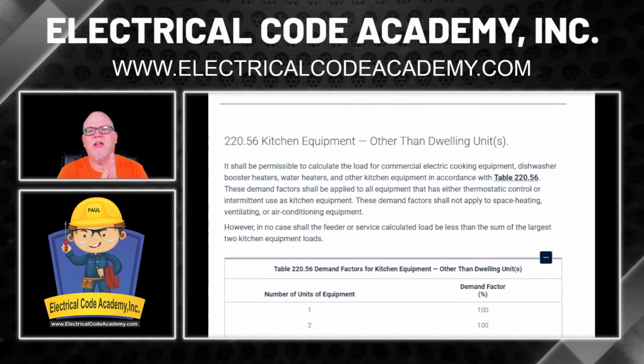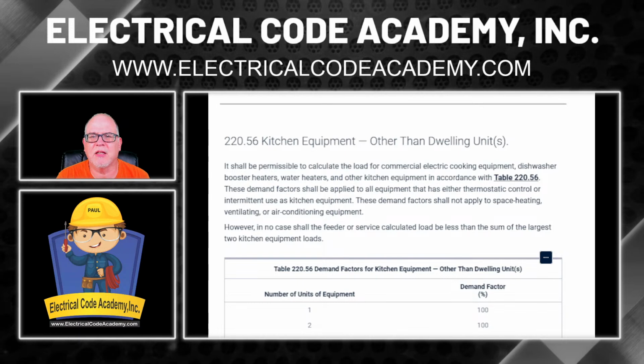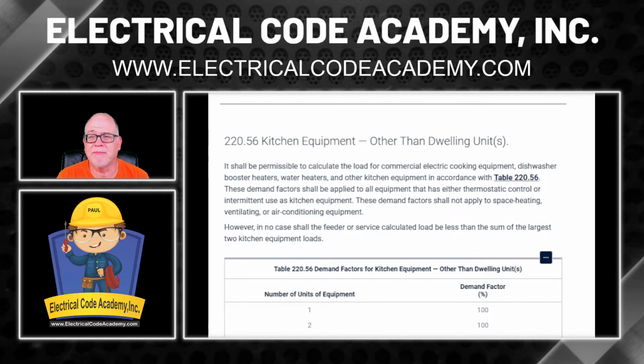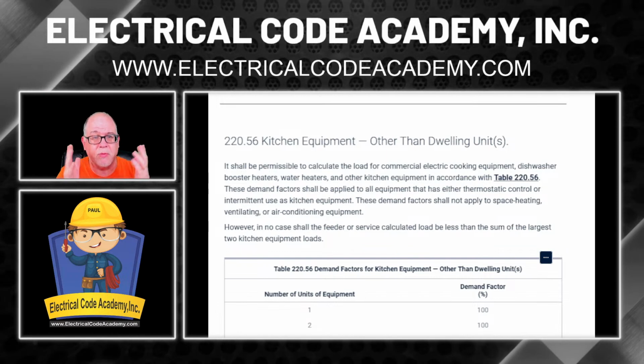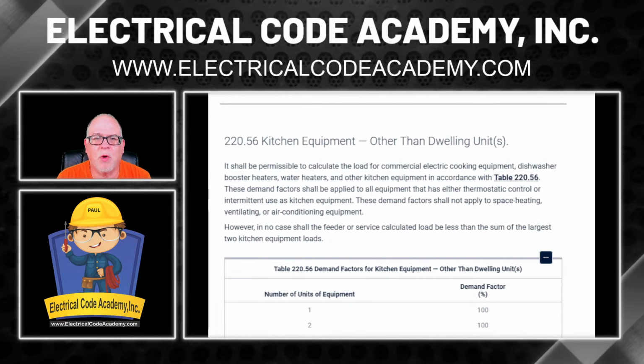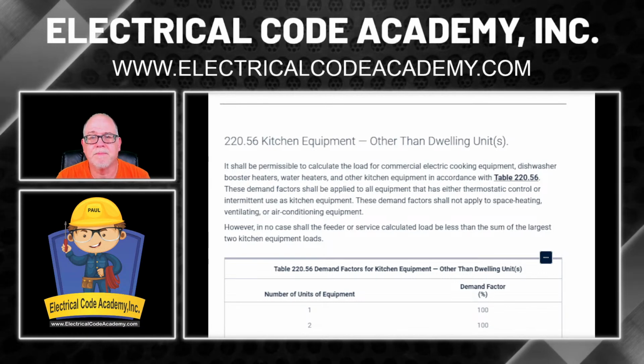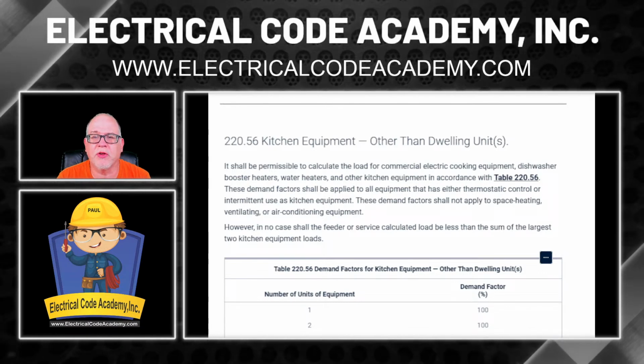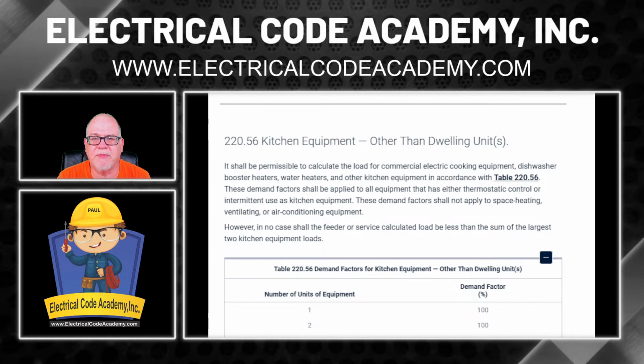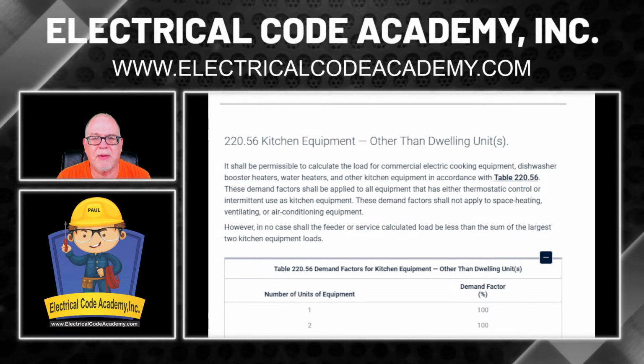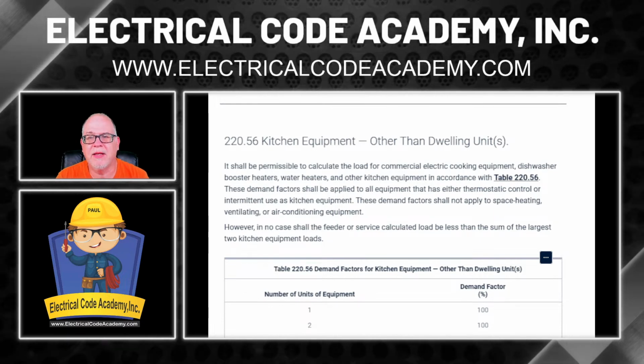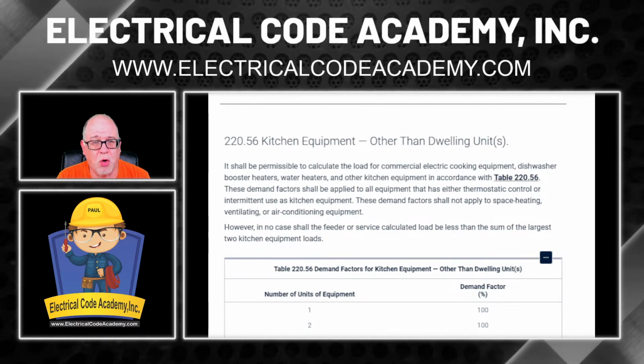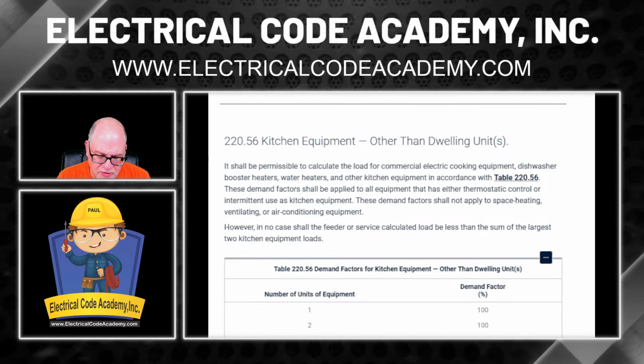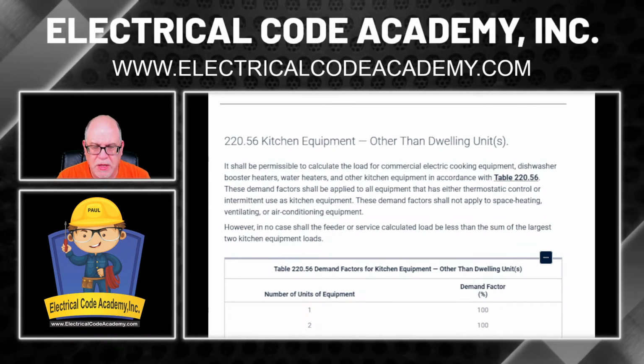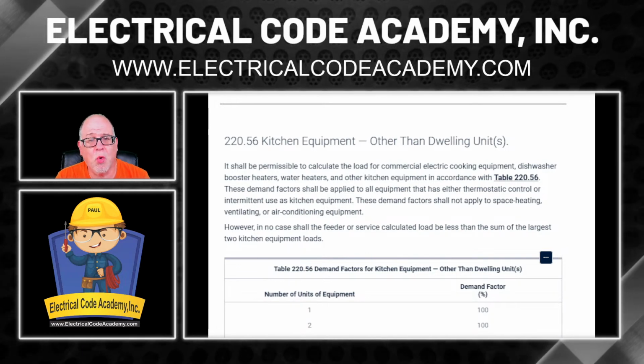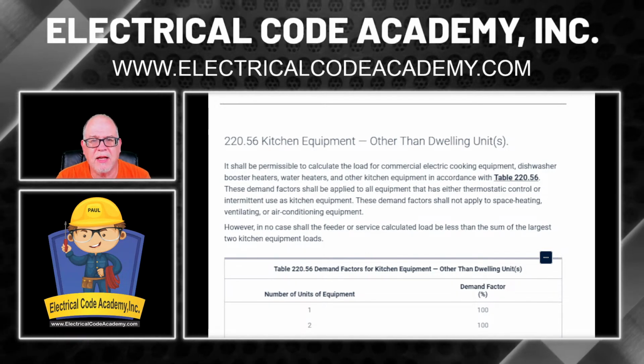So let's read it. It says, it shall be permissible to calculate the load for commercial electric cooking equipment. Okay, so we do have cooking. We have ovens, so we're good there. Dishwasher booster heaters, we do have a booster heater. Water heaters and other kitchen equipment in accordance with table 220.56. It also says these demand factors shall be applied to all equipment that has either thermostatic control, and most of this stuff, the ovens, the grills, the deep fryers, and all that kind of stuff, are going to be thermostatic controlled. It says, or intermittent use in as kitchen equipment.